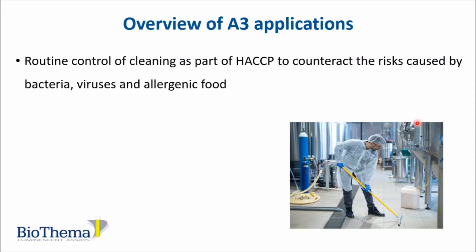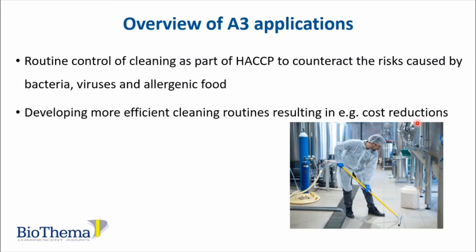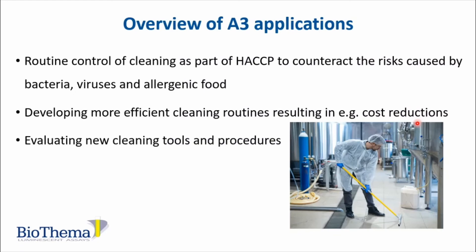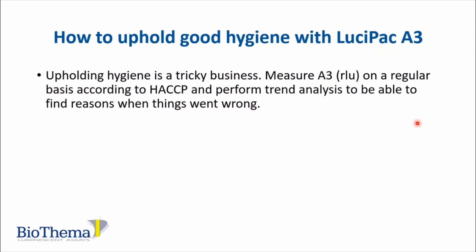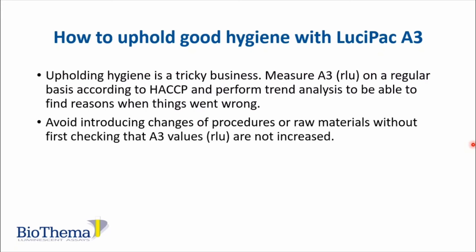Here is an overview of A3 applications: routine control of cleaning as part of HACCP to counteract risks caused by bacteria, viruses, and allergenic food; developing more efficient cleaning routines resulting in cost reductions; evaluating new cleaning tools and procedures; education of staff in hygiene and cleaning; and testing hand hygiene. Measuring A3 regularly according to HACCP and performing trend analysis helps find reasons when things went wrong. Avoid introducing changes in procedures or raw materials without first checking that A3 values in RLU are not increased.